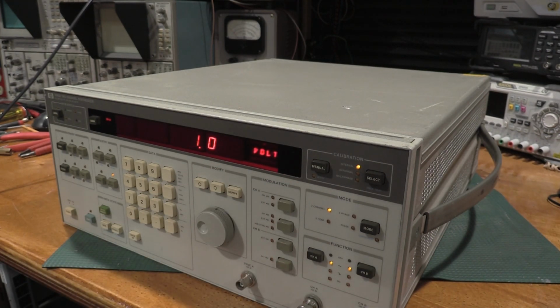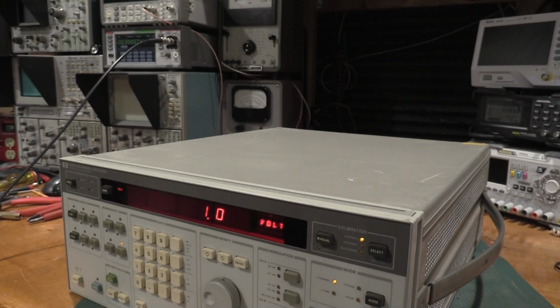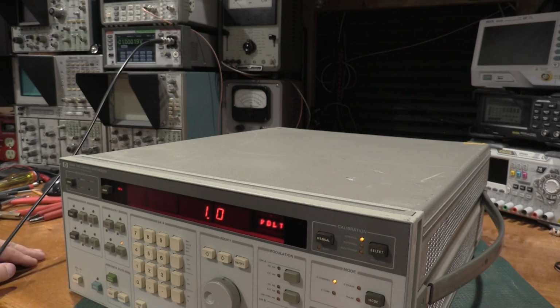If we take a look at the meter, we're at 4, it's bouncing at the 4th digit, which is what this thing's supposed to do. Well within specification, that's good. Channel B is also the same.